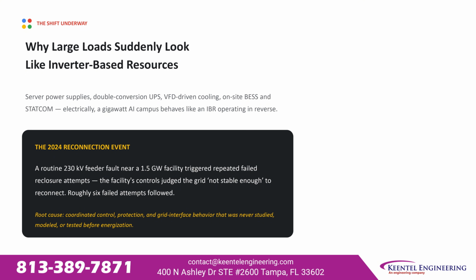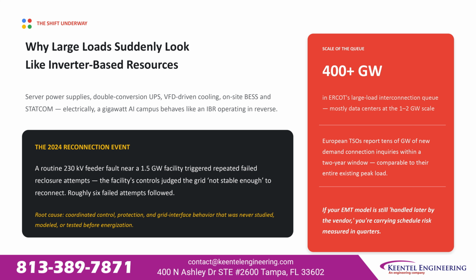Consider the 2024 reconnection event. A routine 230 kilovolt feeder fault near a 1.5 gigawatt facility triggered repeated failed reclosure attempts because the facility's own controls judged the grid not stable enough to reconnect. Roughly 6 failed attempts followed. The root cause was coordinated control, protection, and grid interface behavior that had never been studied, modeled, or tested before energization. And the scale behind this is enormous.